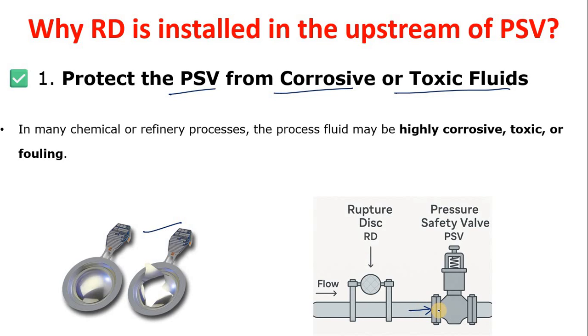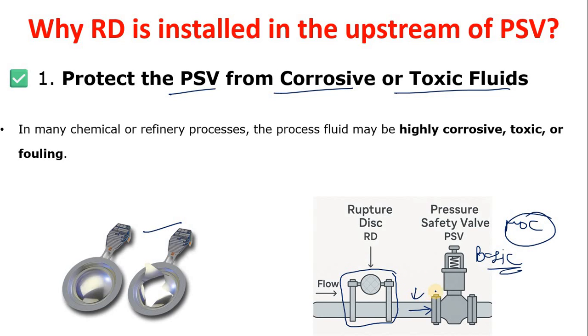You have two options: keep the same material of construction and accept the contact, or upgrade the MOC, which obviously increases cost. However, if you keep the MOC at the basic level — the same as your pipe spec — and install a rupture disk upstream, the RD creates a physical barrier between the process fluid and the PSV internals, protecting them.